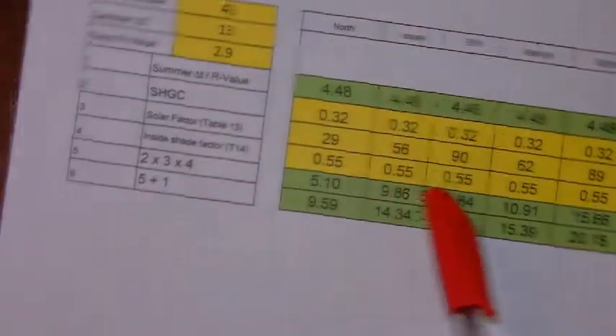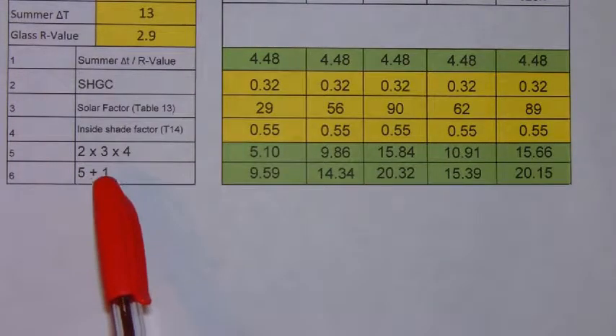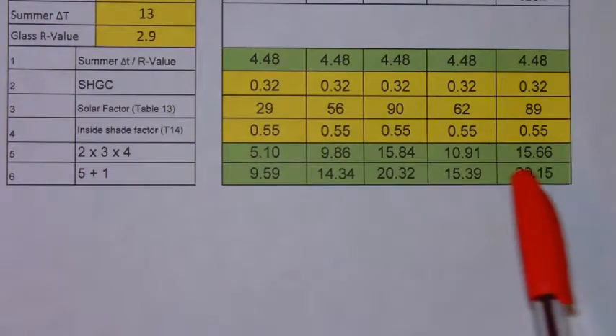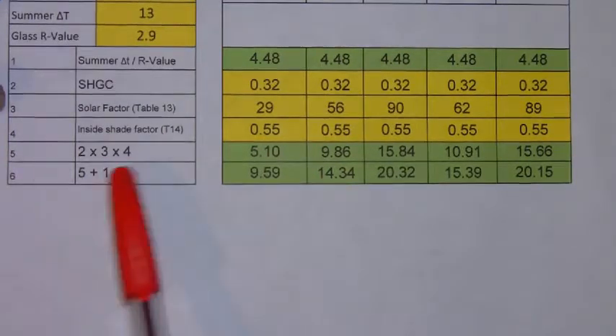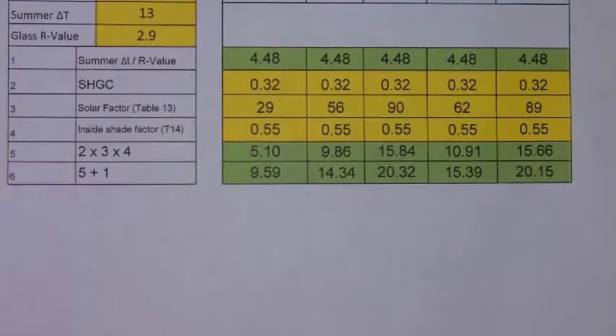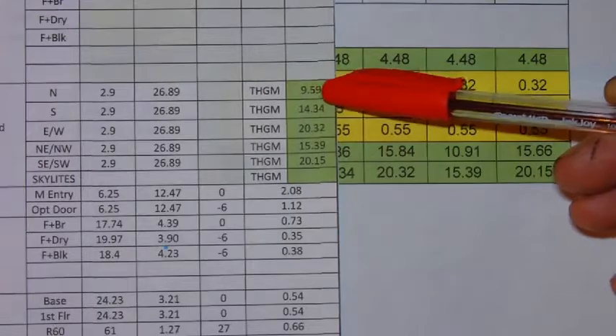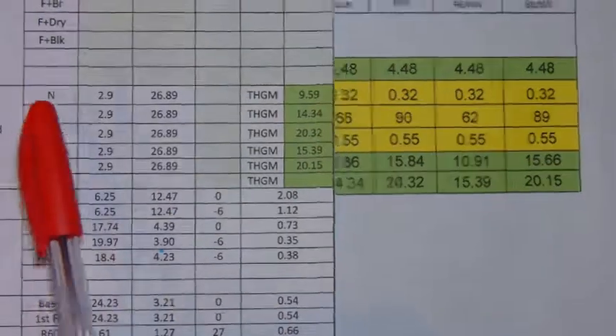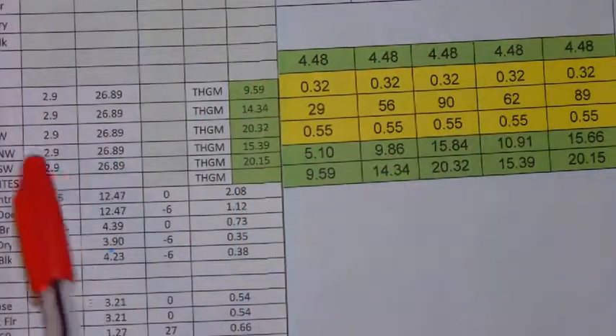That gets entered in here. Next, you simply multiply line 2 times line 3 times line 4 to get these results. And then finally you add row 5 with row 1 to get the total multipliers for your heat gain through glass. Once you have these multipliers, you would insert them onto page 3 in the appropriate row. Make sure that you have the north factors, the south factors, and all the proper factors based on their orientation.